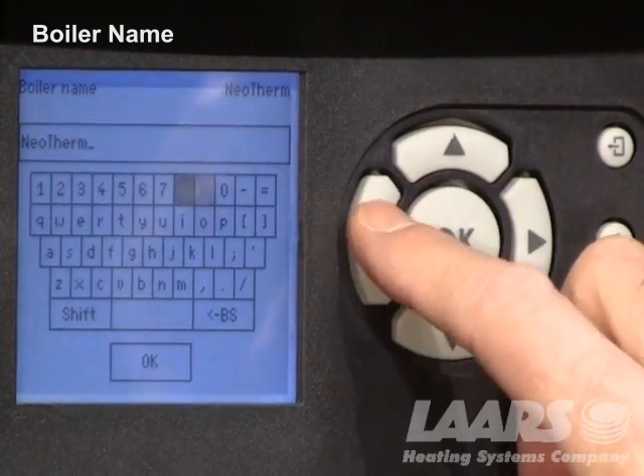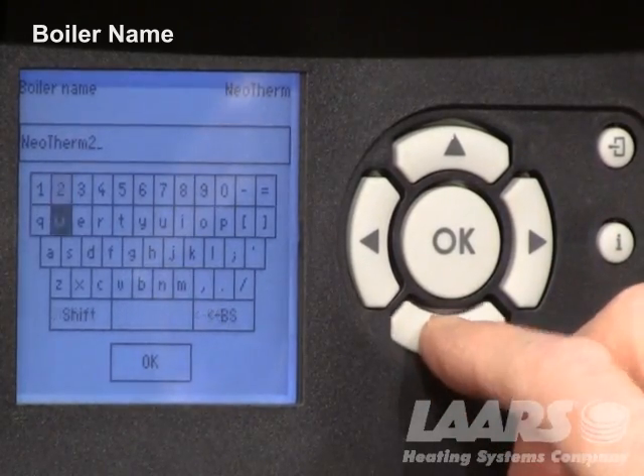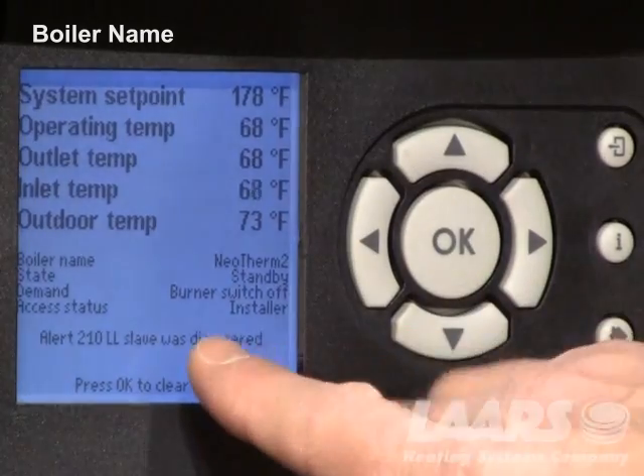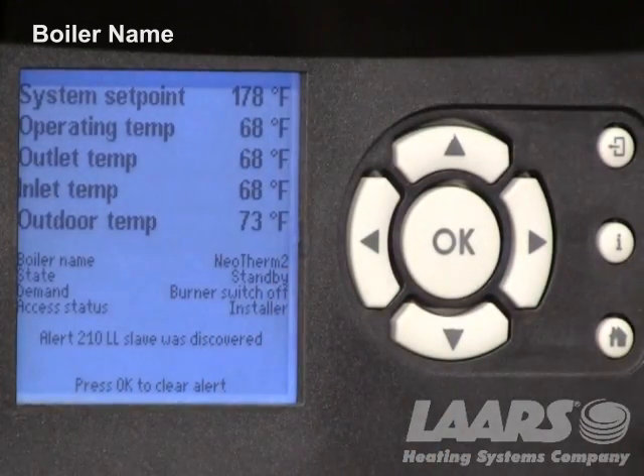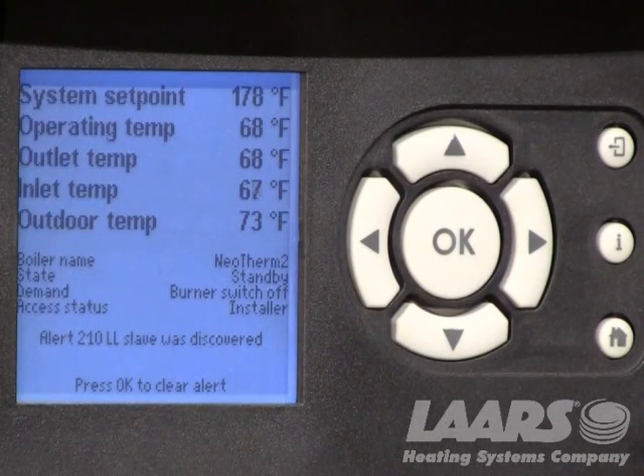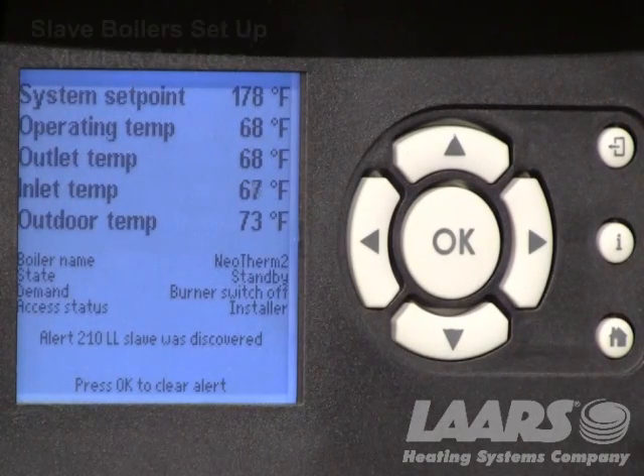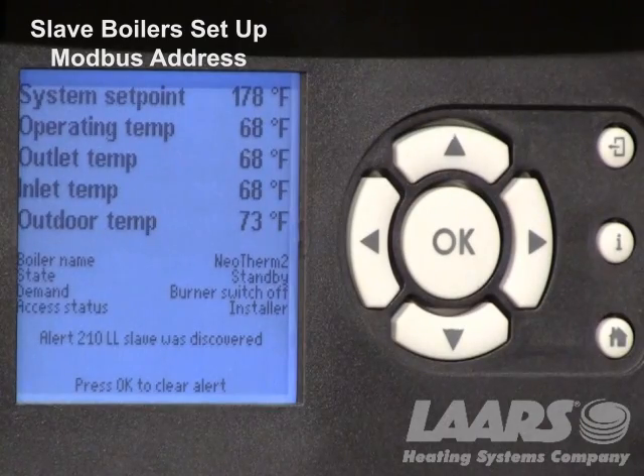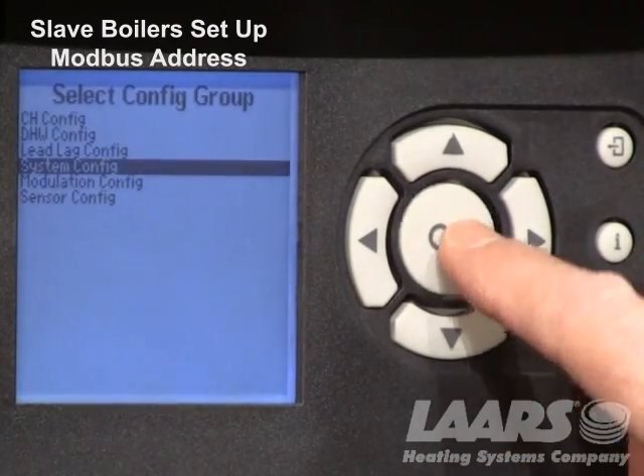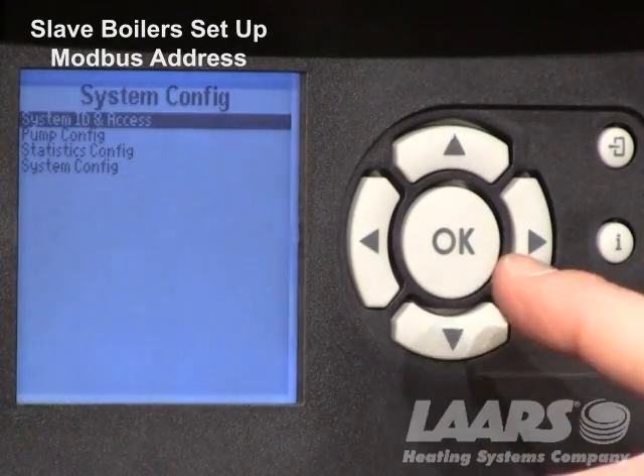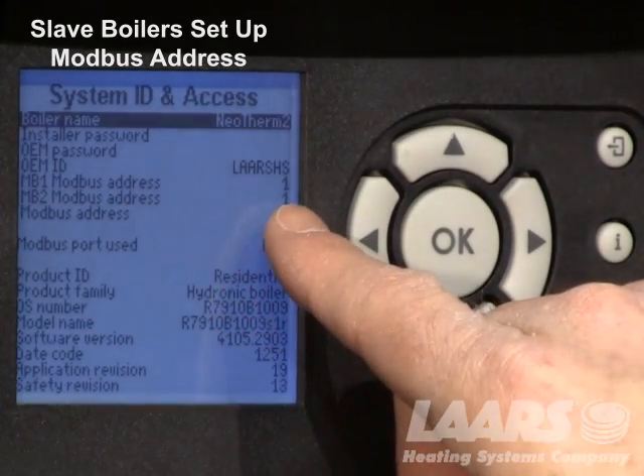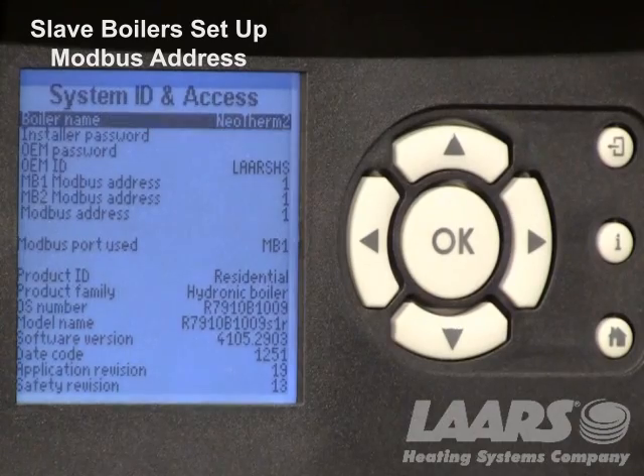If you're on one of the lag boilers — say boiler 2 — highlight boiler 2. Any name will do. Press okay, go back to the home screen, and it will now appear as Neotherm 2. Again, we do not have to change the boiler name to operate the boilers. Now we want to change the Modbus addresses. Go to the information button, choose advanced settings, scroll down to system configuration, press okay. System ID and access is highlighted — press okay. Go down and confirm that on the lead boiler your MB1 address is 1 and your MB2 address is 1. Once confirmed, the master boiler is set up.